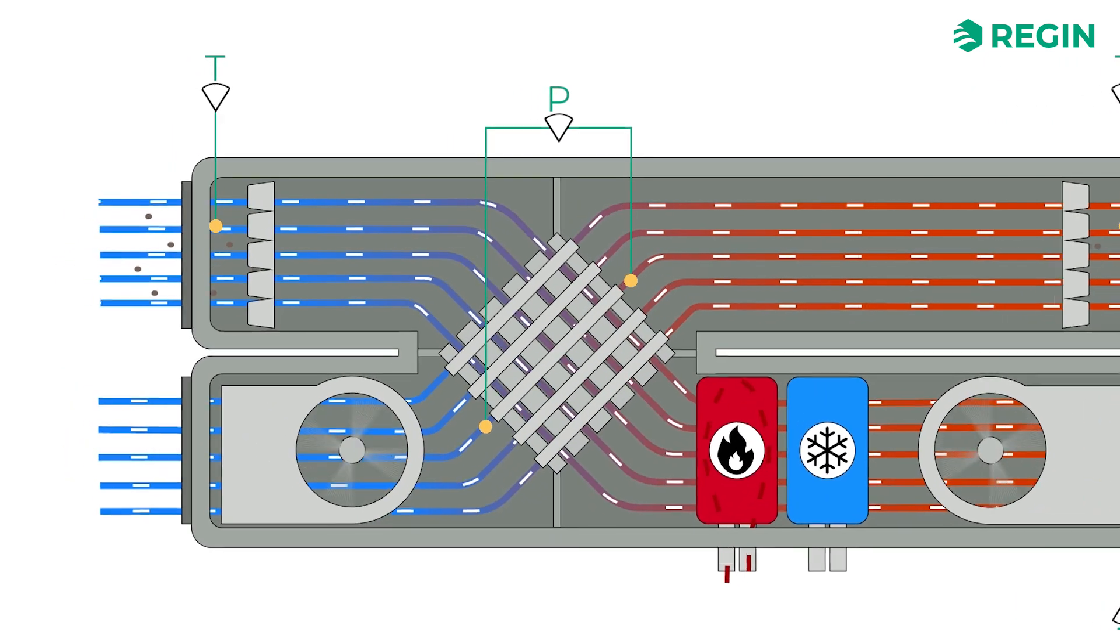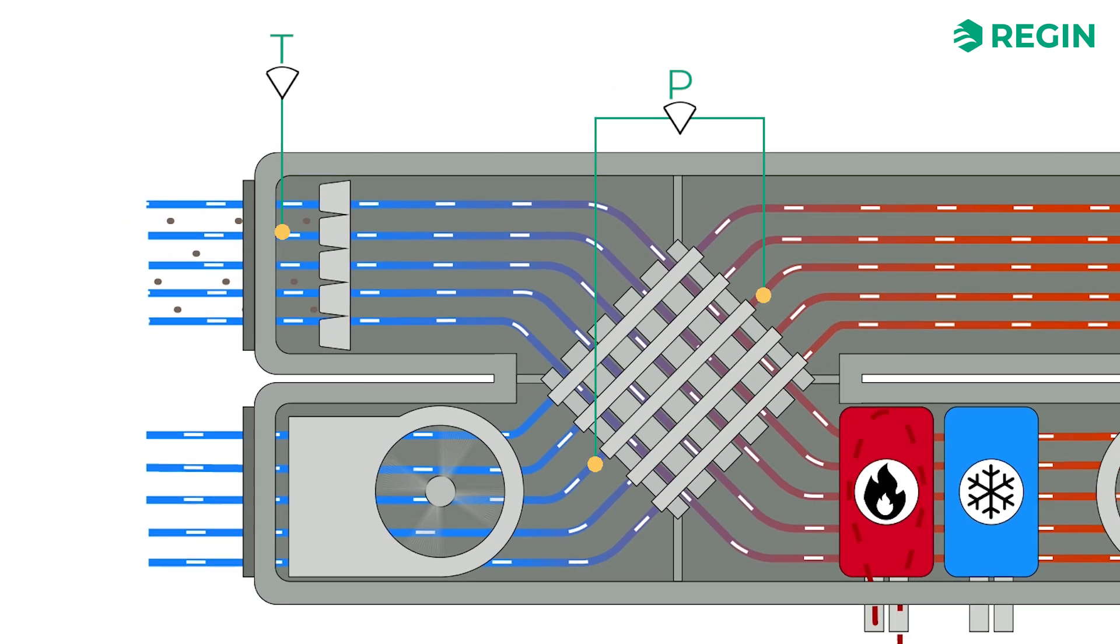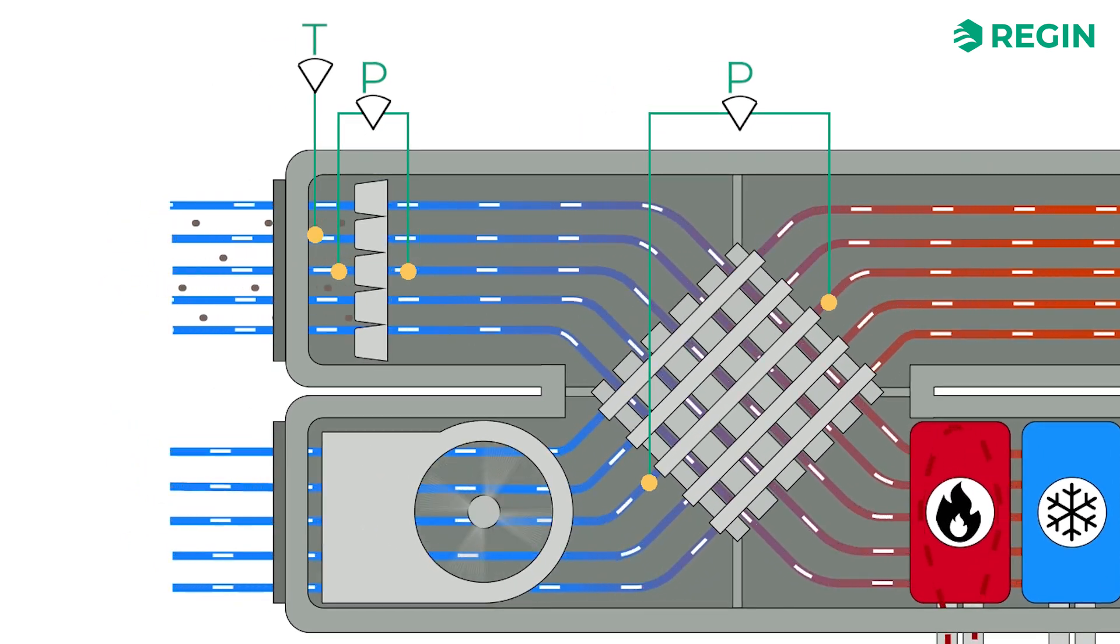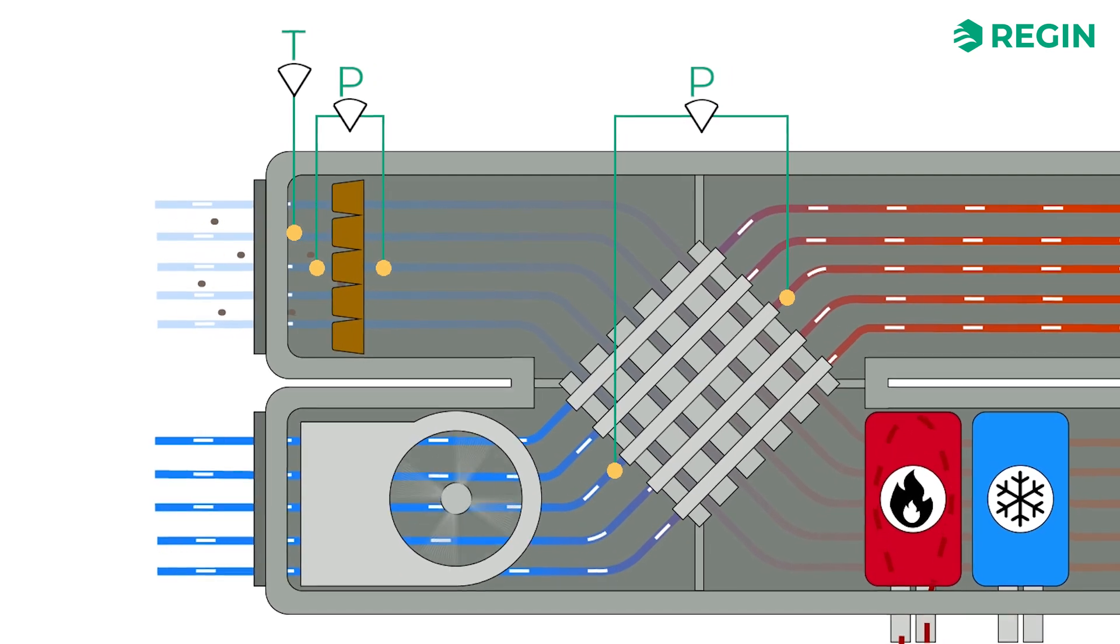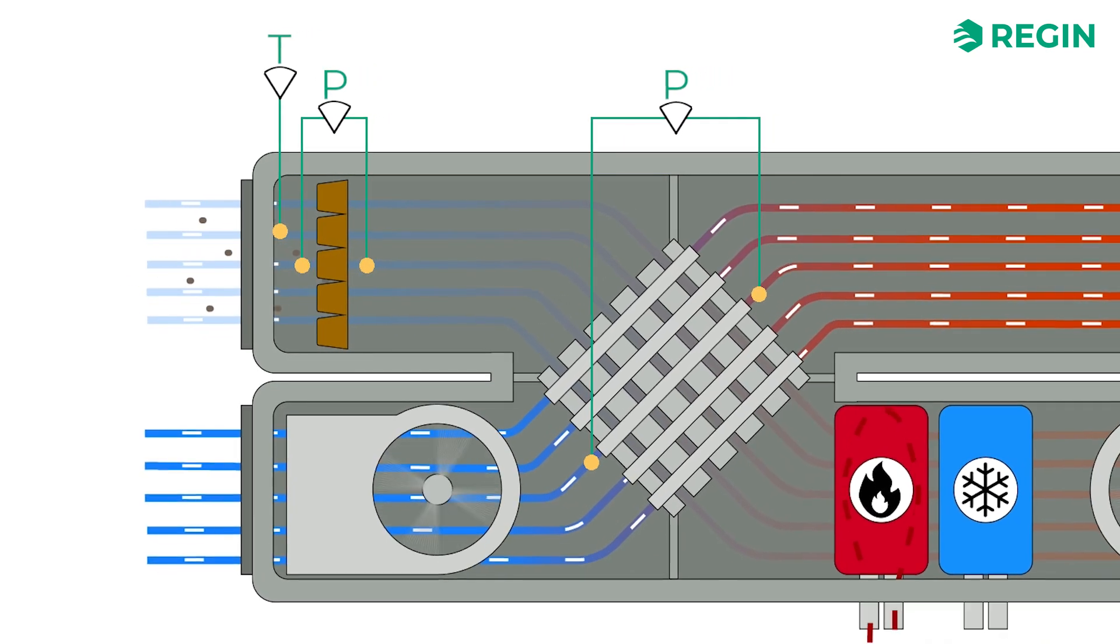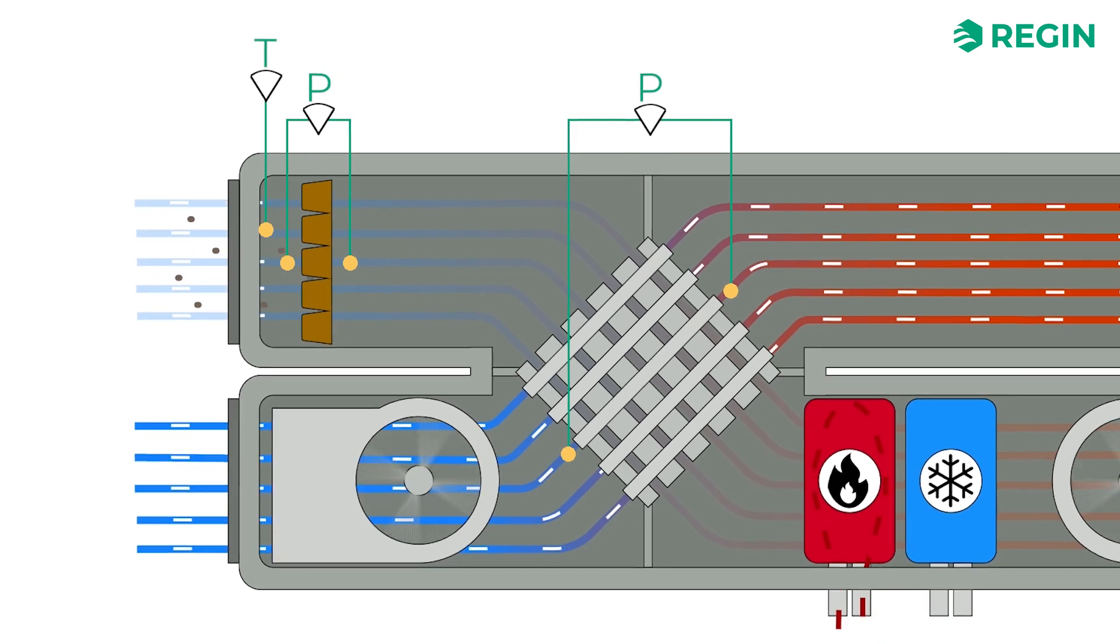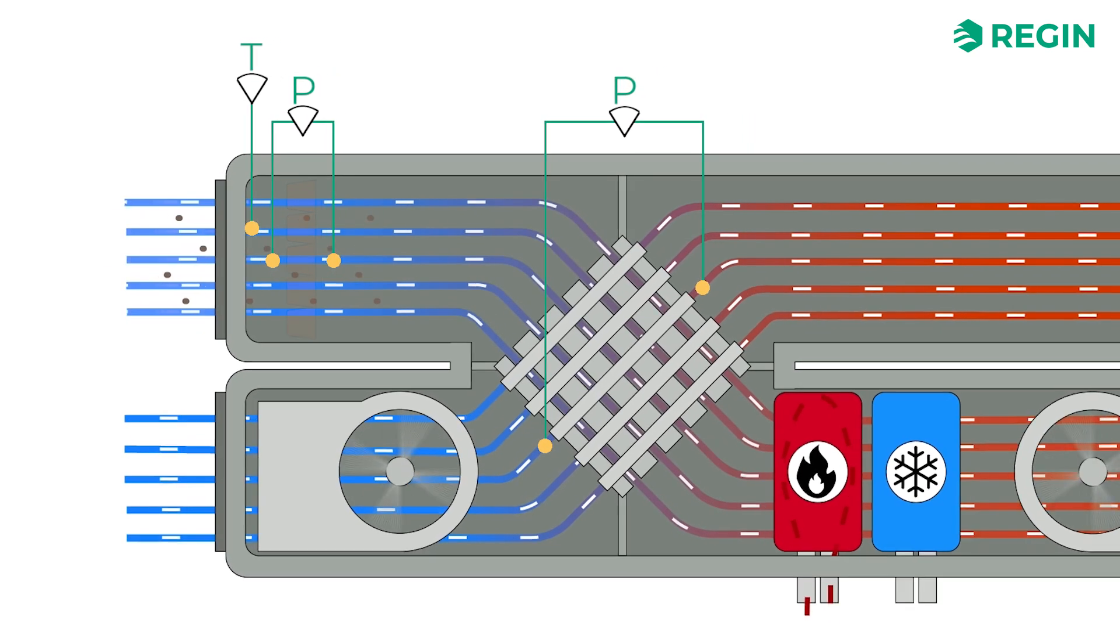Pressure difference is also measured to keep an eye on the status of the particle filters. Over time, accumulated particles will clog up the filters, which makes it more difficult for the air to pass through. In such a situation, the fans will need to work harder to move air in and out, but that requires more energy. So by keeping an eye on the pressure difference over the filters, it will be clear when a filter needs to be exchanged.